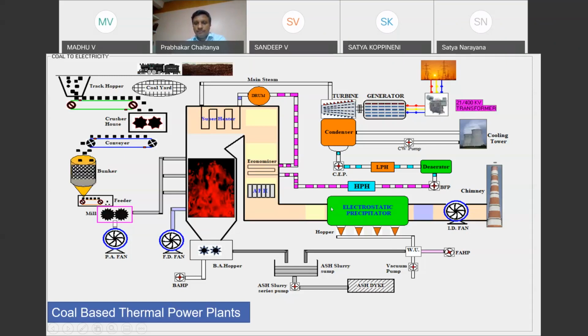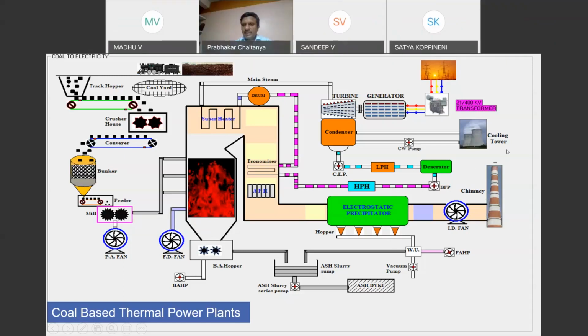Now, there are certain things which we have to look after here. The first thing is emission norms. We should not let the particulate matter go beyond a higher value. There is a limit. For an older plant, the limit is 100 milligram per normal meter cube. The electrostatic precipitator efficiency should be on the higher side, around 99%, so that particulate matter will not come out of the chimney. That we have to ensure. It's a responsibility towards our environment.